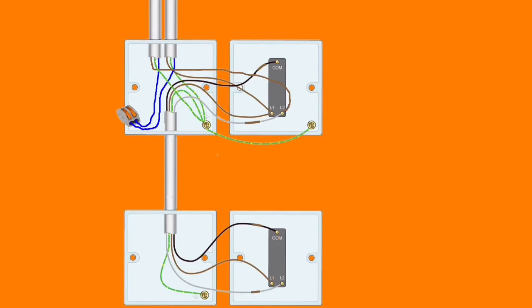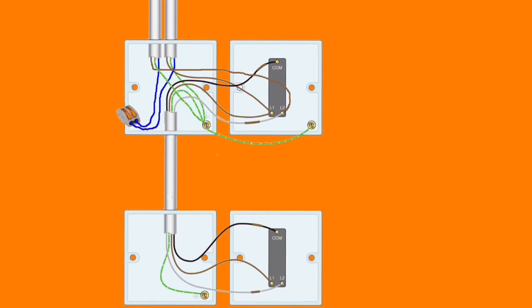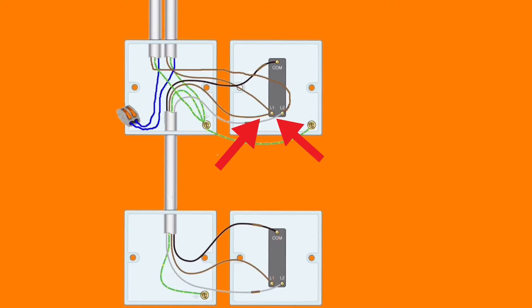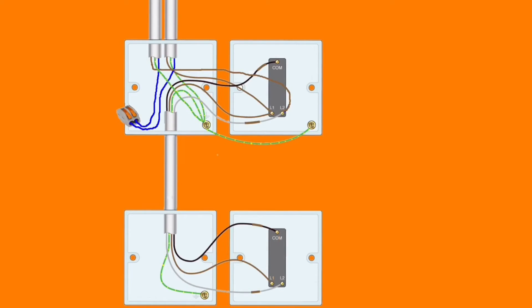And we've used black for common and we've identified that with brown sleeving, and the other two conductors, doesn't matter which one goes in L1 and which one goes in L2. So we've used brown and grey, and again the grey conductor has been identified with brown sleeving because the black and grey are both switching line conductors.